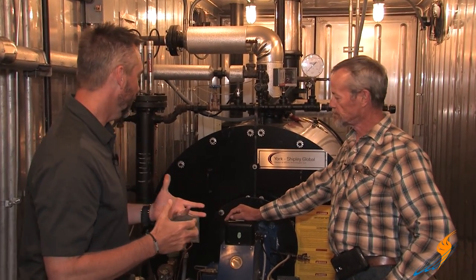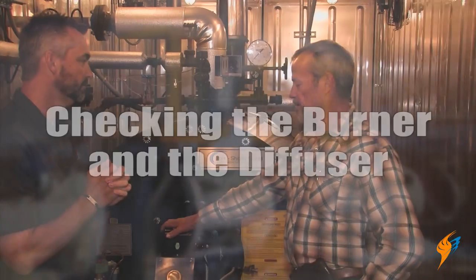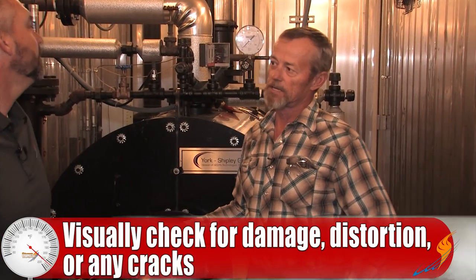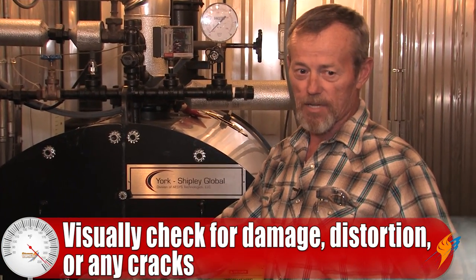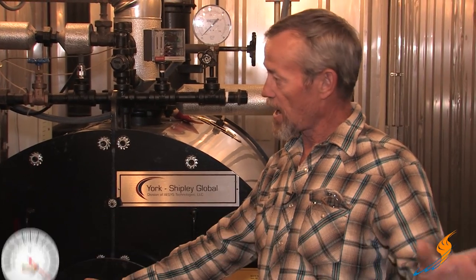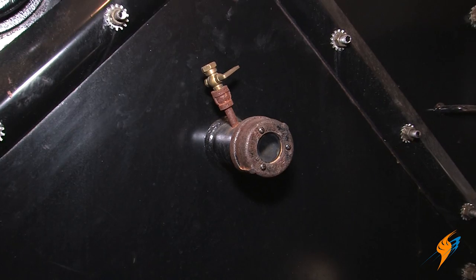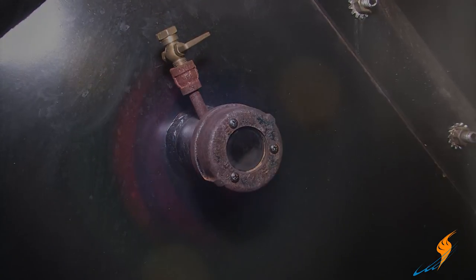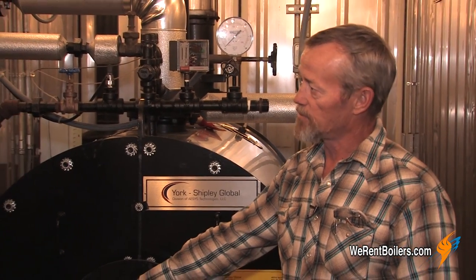Michael, why don't we start first with the burner and the diffuser and talk about what we need to do for the monthly maintenance with that? You just need to visually check it to see that it's not distorted, cracked, or burnt up. Typically you would turn the burner down to the low fire rate and then look in the back peep sight — at low fire rate you can see the diffuser and tell if it's distorted, burnt up, or has cracks in it.